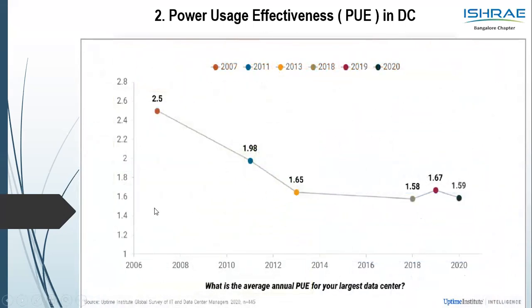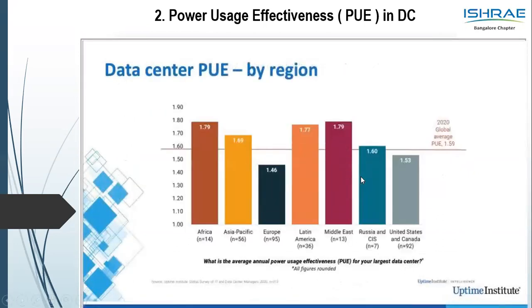In 2006, 2007, when the data center concept started, we were looking at 3, 2.5. With energy efficiency, free cooling, and different energy consumption and variation in innovation, the PUE dropped. Today, as we talk, the figures for last year, January to December, showed a PUE average of around 1.59. Again, it depends upon various factors: location, the type of cooling, the type of rack, the type of data center, but on average it is 1.69, 1.59. If you divide this PUE into different locations or areas, the average, as I said, is 1.59, and you could find the average PUE for different locations. In a few countries, you have the benefit of lower ambient temperature, and thereby your PUE also drops.